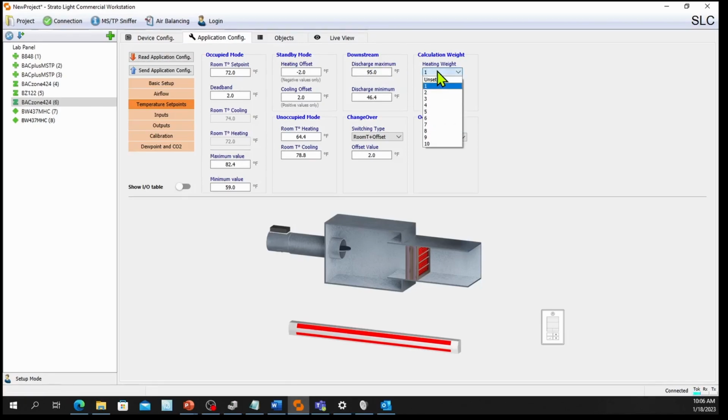You can give your box a weight if the system is a VVT type system. Unoccupied set points can be set individually for heating and cooling. Changeover, when the upstream is hot or cold, is determined by either comparing the upstream air to the zone temp, or it can be given a constant value. If the air in the duct will always be cold, you can disable the changeover.